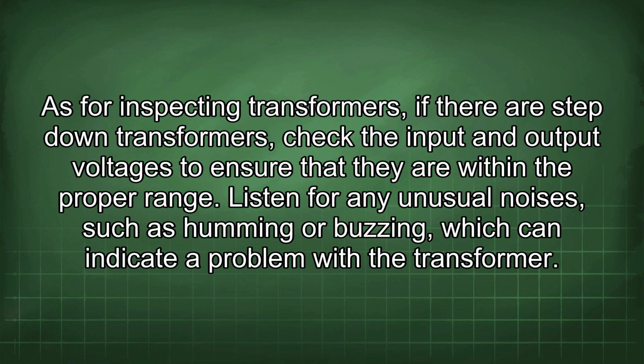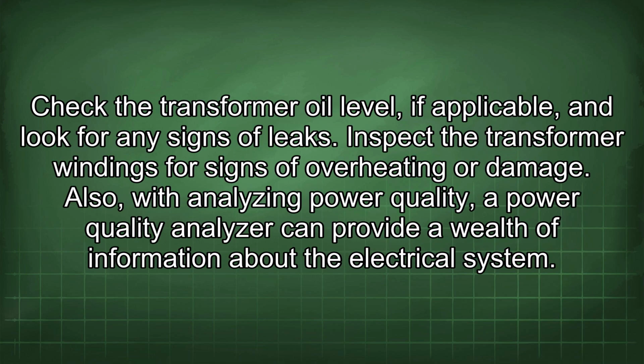As for inspecting transformers, if there are step-down transformers, check the input and output voltages to ensure that they are within the proper range. Listen for any unusual noises, such as humming or buzzing, which can indicate a problem with the transformer. Check the transformer oil level, if applicable, and look for any signs of leaks. Inspect the transformer windings for signs of overheating or damage.